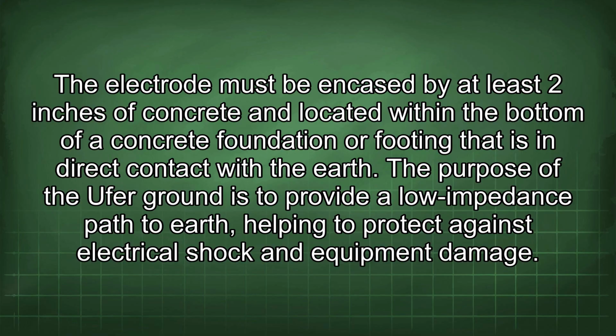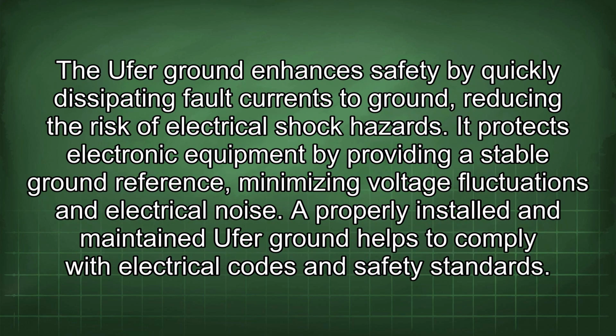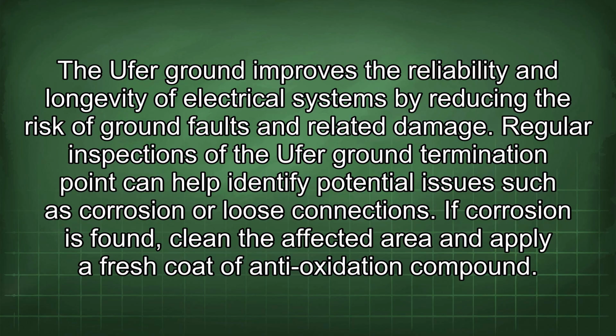The purpose of the Ufer ground is to provide a low impedance path to earth, helping to protect against electrical shock and equipment damage. The Ufer ground enhances safety by quickly dissipating fault currents to ground, reducing the risk of electrical shock hazards. It protects electronic equipment by providing a stable ground reference, minimizing voltage fluctuations and electrical noise. A properly installed and maintained Ufer ground helps to comply with electrical codes and safety standards. The Ufer ground improves the reliability and longevity of electrical systems by reducing the risk of ground faults and related damage.